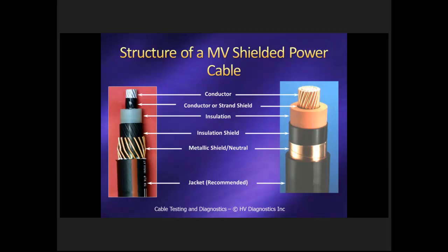Partial discharge testing on a cable can only really be done down the cable. In other words, you can look down a cable if you have a shielded cable. So if you don't have a concentric neutral or a tape shield type construction, it is extremely difficult, if not impossible, to look down the cable. And that's a very important part of understanding the cable and trying to apply partial discharge. You need to make sure there's a shielded cable.